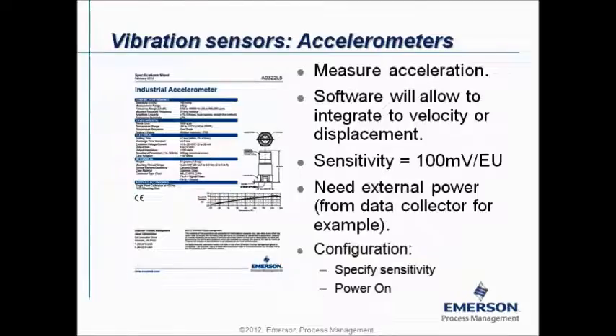Now, to measure the vibration signal, we are working with two kinds of transducers. One transducer is called an accelerometer, and here you see a typical data sheet of an accelerometer and a drawing. It measures acceleration, but the software can integrate it into velocity or displacement. What is quite important to know is that every sensor has a certain sensitivity, and the sensitivity is a relation between the volt signal and the vibration signal. An accelerometer normally needs power from the data collector, so in the configuration you always have to specify what the sensitivity is, and you have to power it from the analyzer.